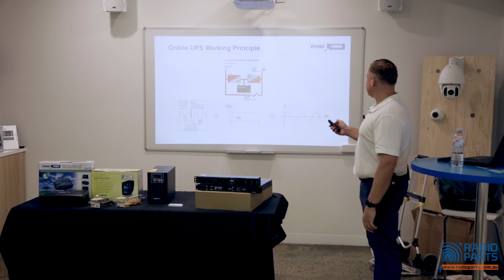Important accessories. This is something that often gets overlooked, particularly with the customers that have smaller sort of things. So, external maintenance bypass switch. This is one of our rack mount units. This allows us to take the whole UPS away without disrupting the load. So this will typically be a make before break switch. As you rotate the switch, it'll be set up where it'll have an alternate input supply. When you switch that across, it connects the other output before it breaks the other input, and that allows the load to see no difference.